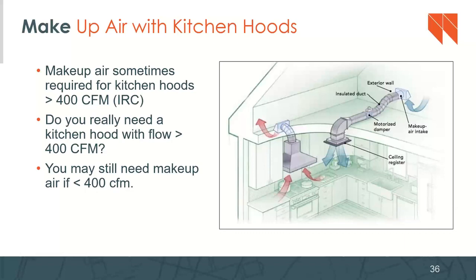We've got that on the next slide, the anatomy of what a makeup air system might look like. You've got your range hood here, it's going to the outside. And then the makeup system here could be a vent to the outside, right through the wall. There's going to be a duct, a motorized damper, and maybe a ceiling register. When the exhaust fan for the range hood is turned on, the motorized damper opens and acts as a relief to bring that makeup air in and keep the pressure in the space balanced. The outside air is being brought in, driven by the exhaust fan. There's no other fan in this system except for the exhaust fan.